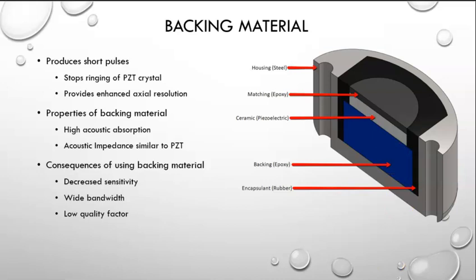So the consequences of utilizing a backing material give us decreased sensitivity to sound, because it's going to be absorbing some of our sound. It's going to give us something called a wide bandwidth, which is very important, and it gives us something called a low quality factor. I'll go over what those two terms are in a minute. The most important thing to remember to begin with is that the backing material stops the ringing of the PZT crystal. That's the most important thing to remember. Now, let's talk about bandwidth.